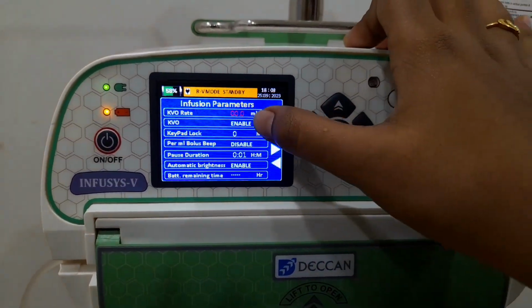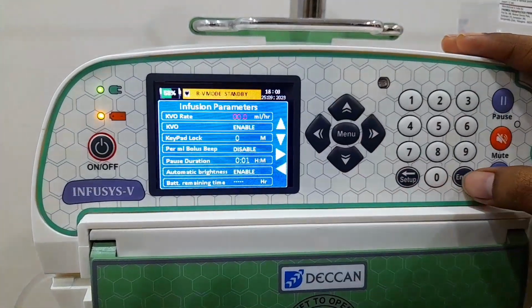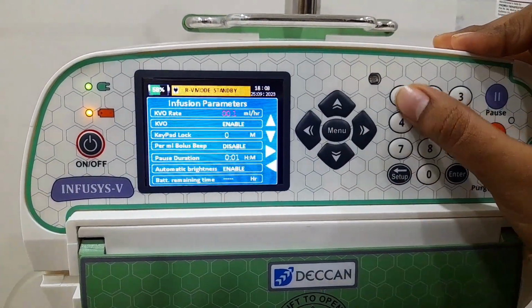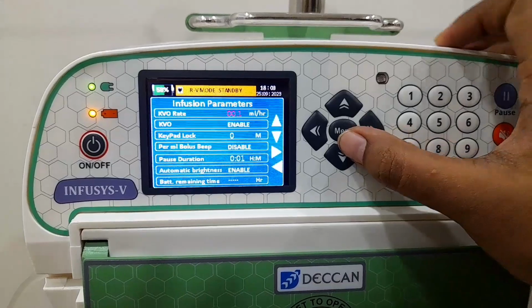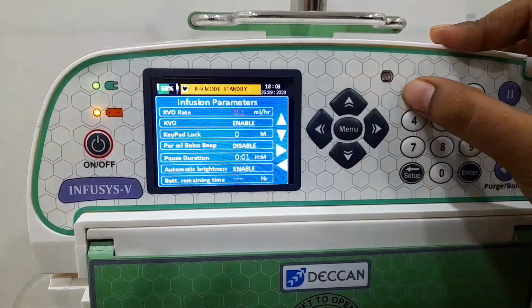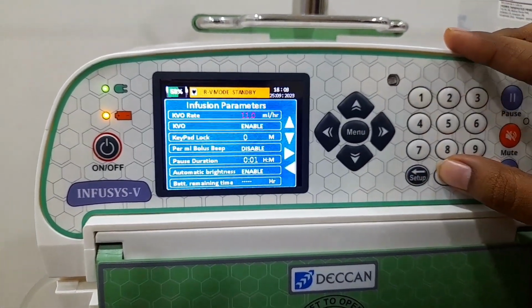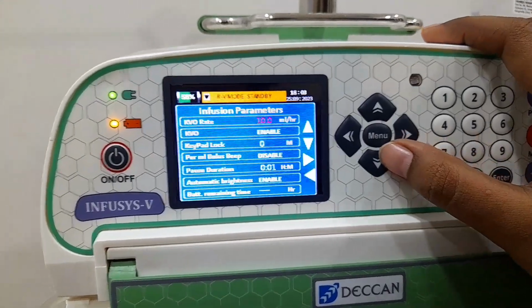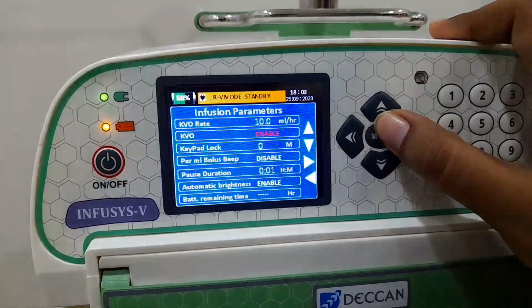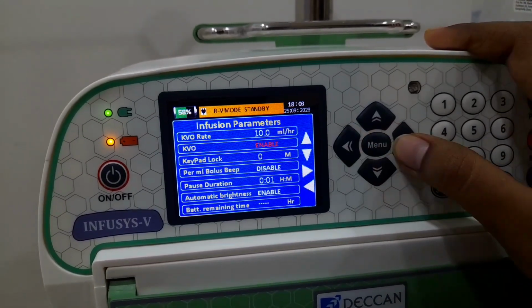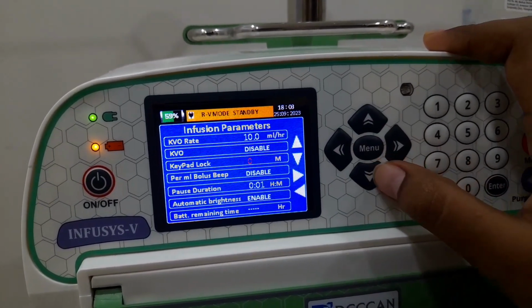In numeric keys, we can set the KVO rate, which ranges from 0.1 to 10 ml per hour in ml per hour mode selection, and a constant 3 drops per minute for drops based selection. When the target volume is reached, the KVO starts to run if KVO is enabled. Since KVO is adjustable, make sure of the KVO rate before starting the infusion. At that time the status bar indicates KVO running.